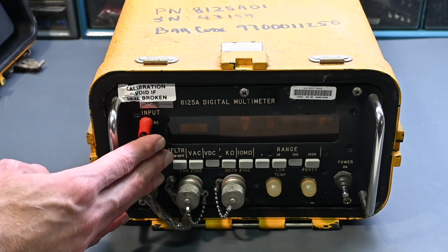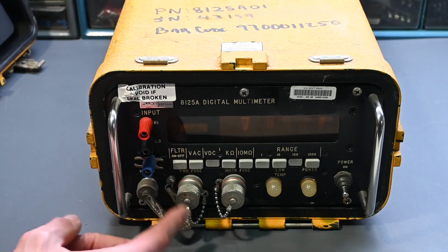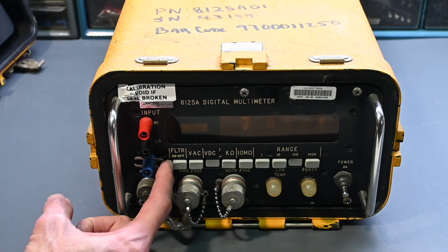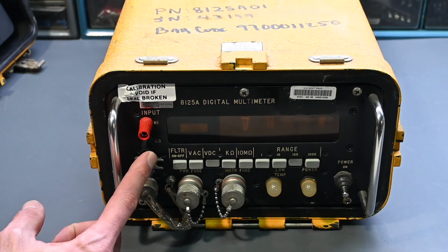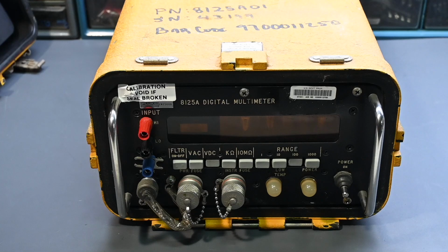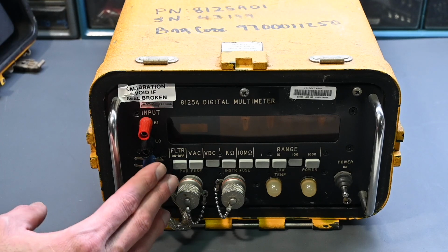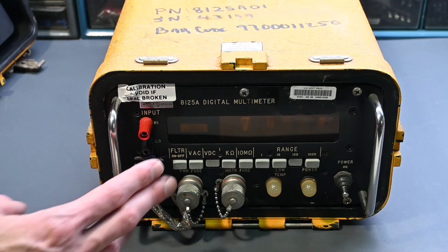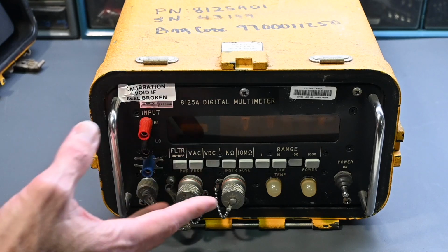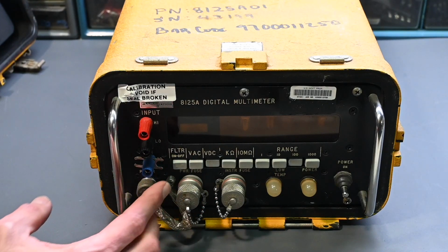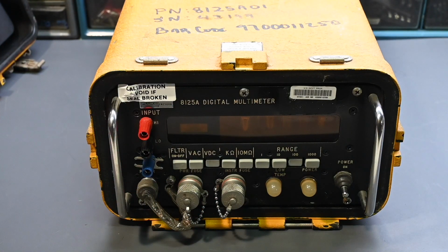Now we have the binding post here for the test leads. The high, low, and ground connection has a jumper link right here for ground, so you can tie ground to low or float the inputs. There's a limit on the voltage if these are floating, how much it can float above the ground connection, or the chassis I should say. That can't be exceeded, but nonetheless it can be broken right here.